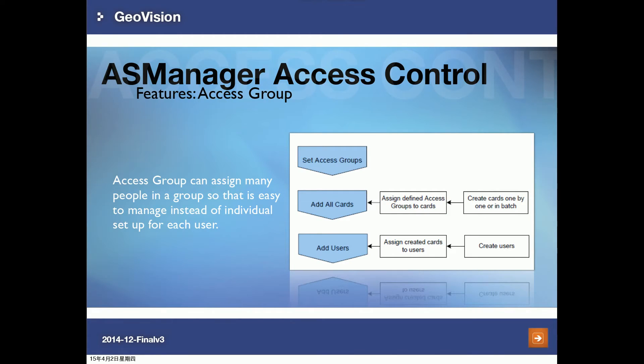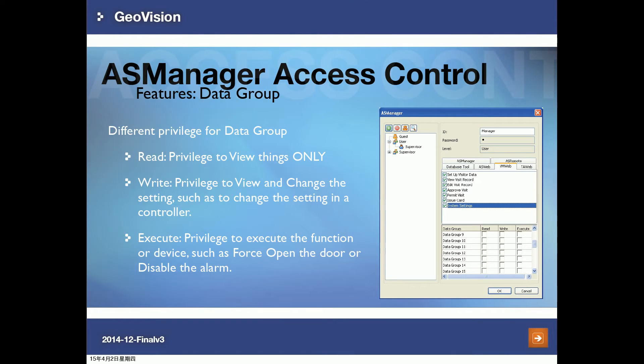The access group function lets you assign many users to an access group for easier management. You set up an access group, add multiple cards or users to it, and each group can have its own access schedule. The data group function is used for different companies within a building — each company has its own data group with its own privileges. The three privilege types are: read (view settings), write (change settings or access control schedules), and execute (open doors or disable alarms within their own data group).